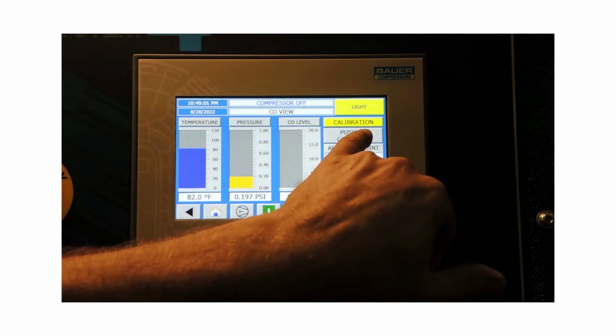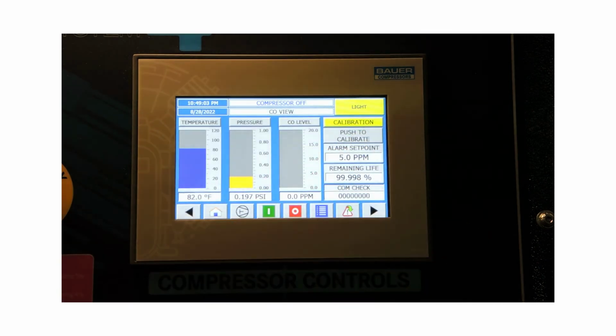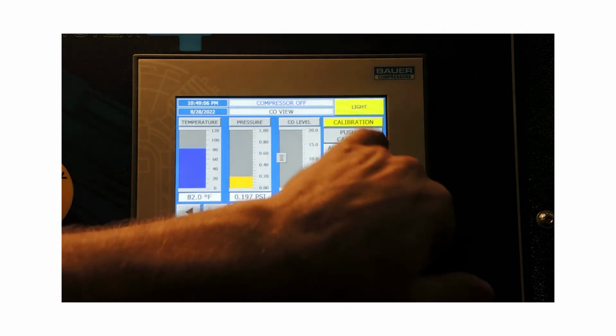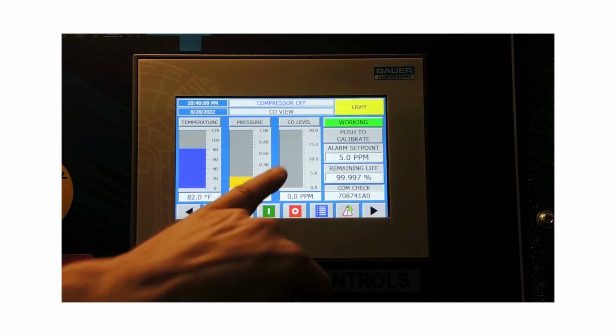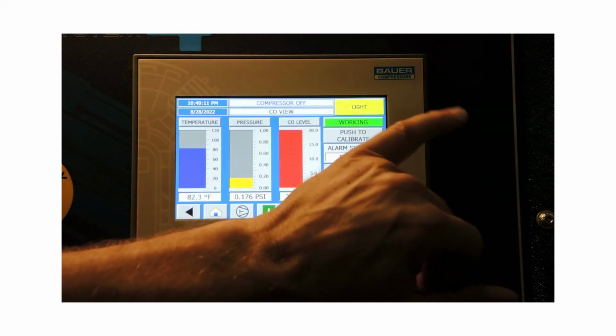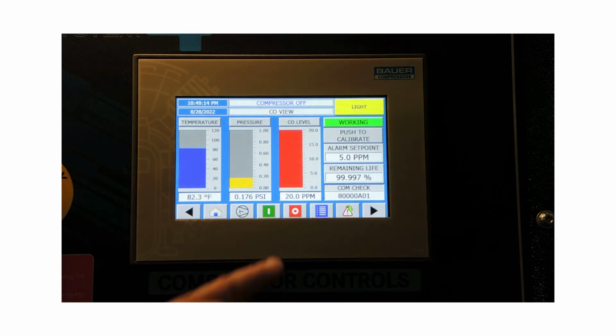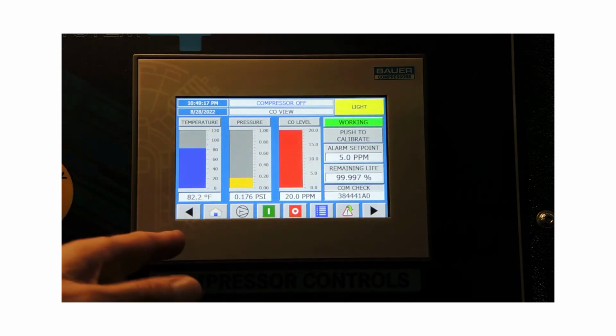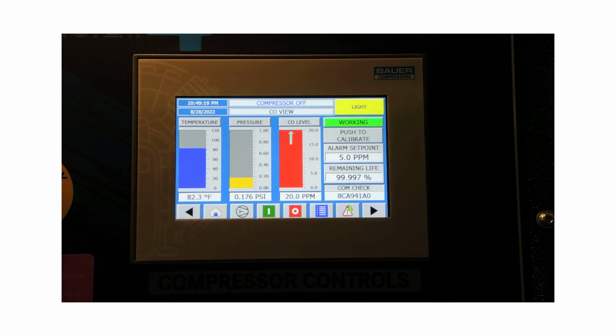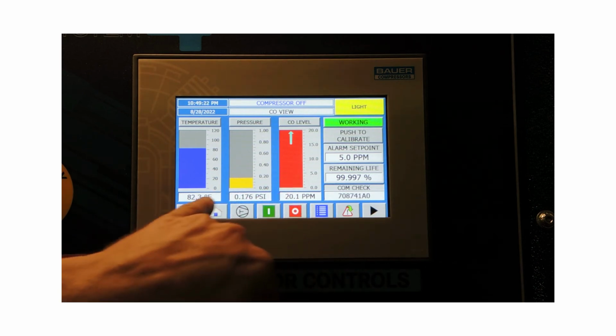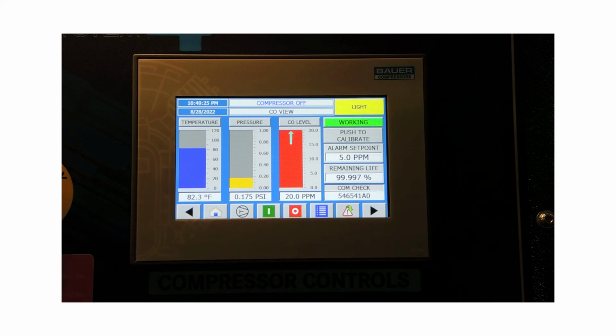Now I'm going to go back into push to calibrate, push to complete. I may have to do that a couple of times. I just want to make sure that it recognizes. There we go. Exit. So it's now saying exit, and now I can verify that the last gas that I used was a 20 part per million gas, and it is reading 20 part. Got pressure, got temperature, and now I've calibrated the CO monitor system. I'll go ahead and note that in my log or put a sticker on the compressor. I'll disconnect the 20 part and let it air out.